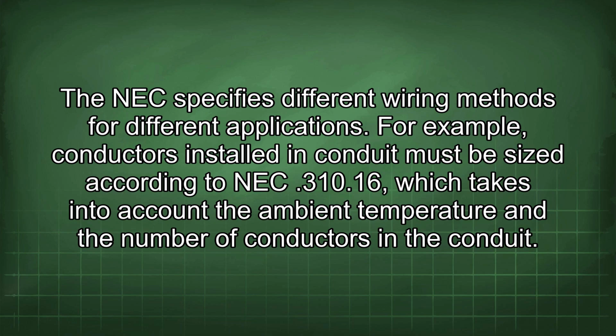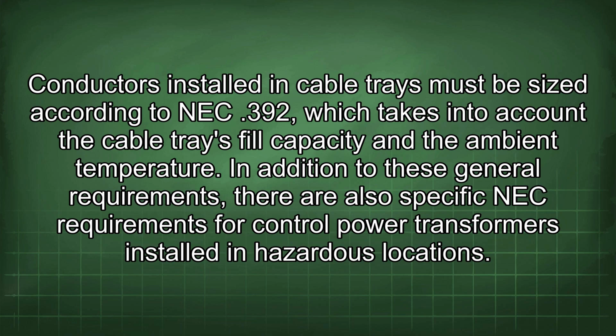For example, conductors installed in conduit must be sized according to NEC 310.16, which takes into account the ambient temperature and the number of conductors in the conduit. Conductors installed in cable trays must be sized according to NEC 392, which takes into account the cable tray's fill capacity and the ambient temperature.